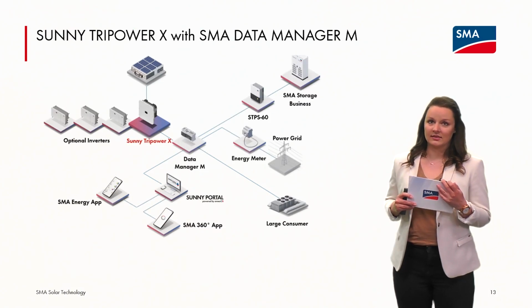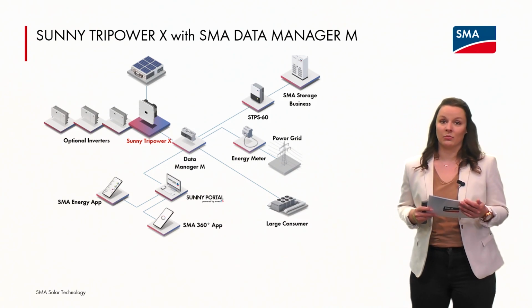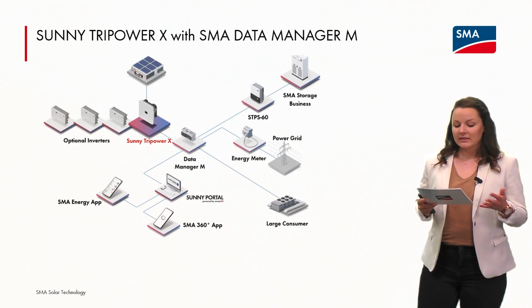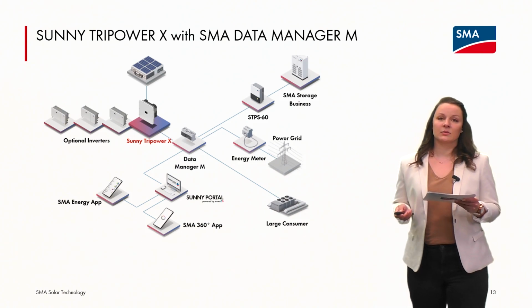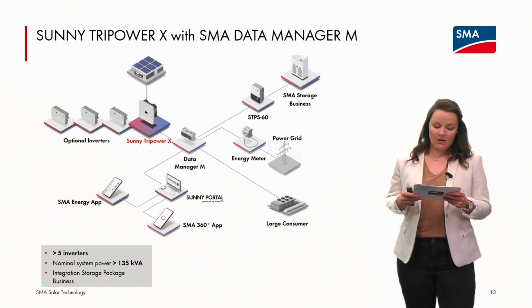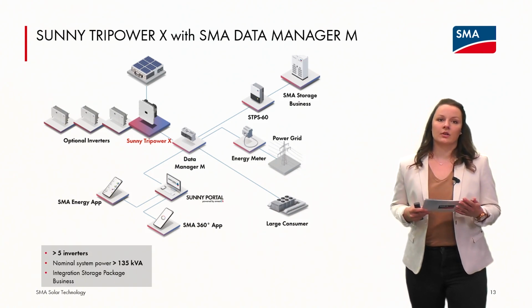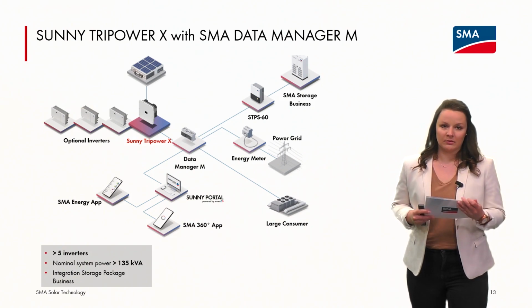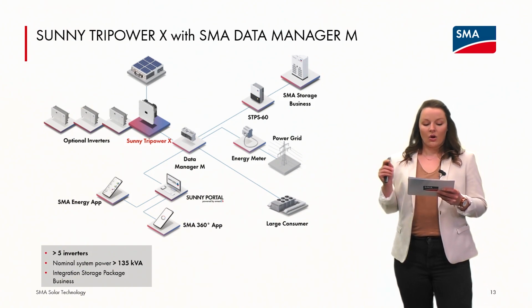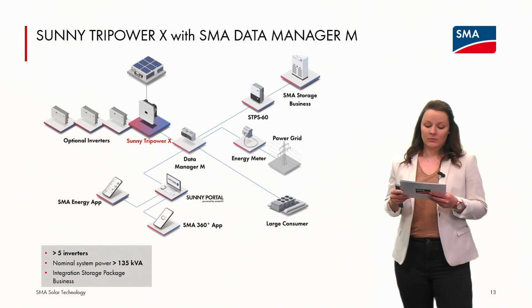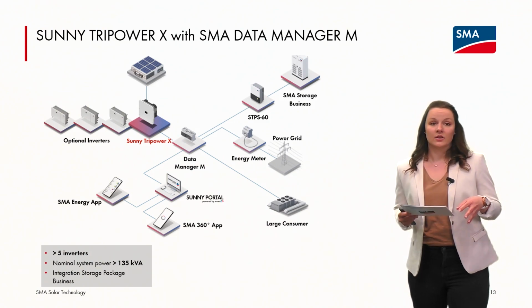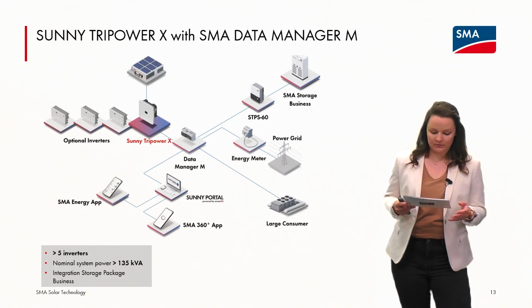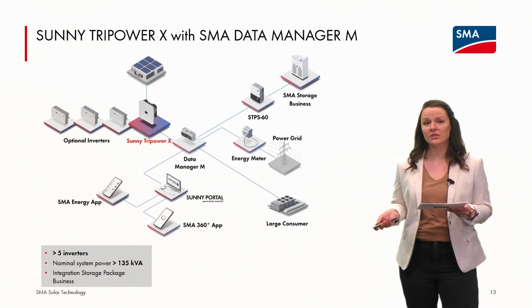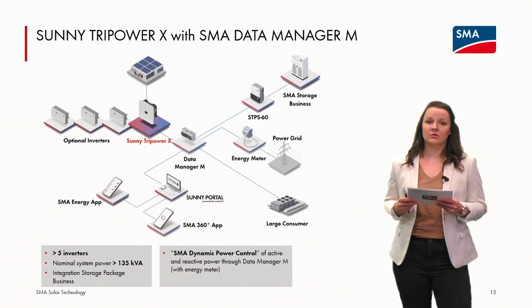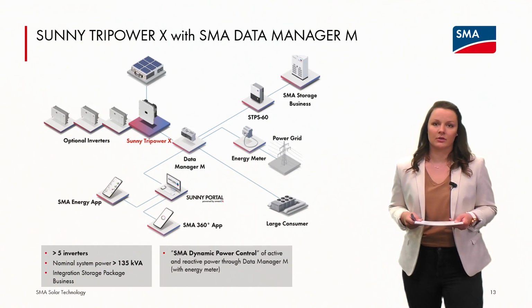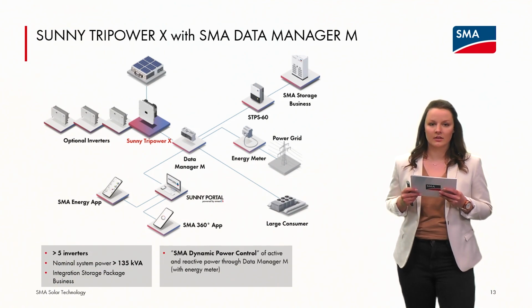Let's look at the system with an SMA Data Manager M. When do we need it? The SMA Data Manager M is needed for systems with more than 5 inverters or more than 135 kVA nominal power. We also need a Data Manager M if we want to integrate a storage with the Sunny Tripower storage. And of course, the Data Manager also offers SMA Dynamic Power Control of active and reactive power.